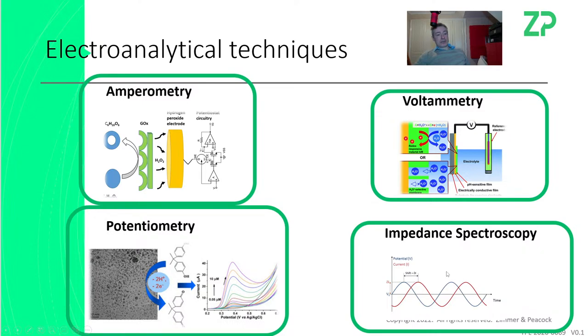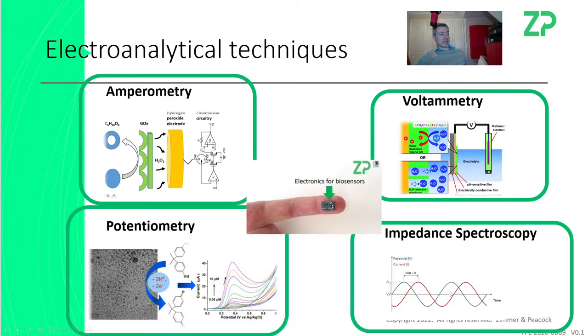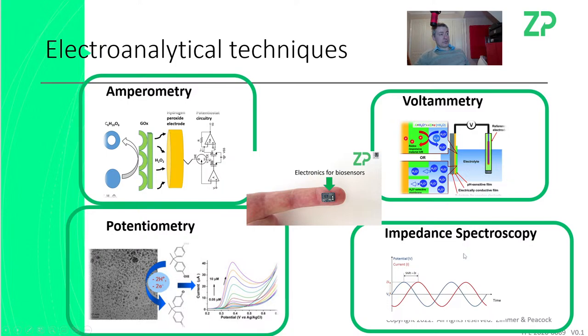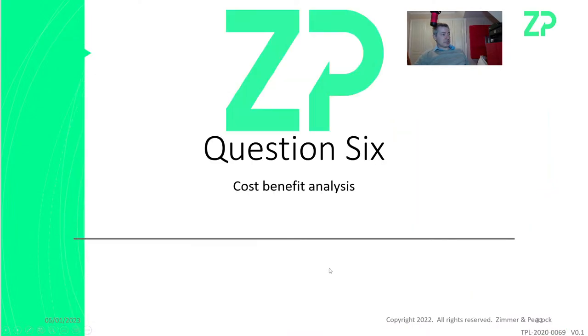That potentiostat doesn't do impedance spectroscopy — there's a different model for that. But it's okay to start, since most of our sensors are either amperometric or potentiometric. We do use impedance for the conductivity sensors, though.